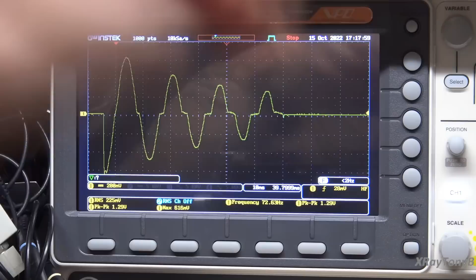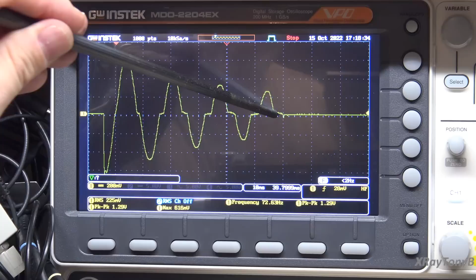So when we get out to about the fourth pulse, you're just a little bit over 20 volts, let's say 22, 23 volts. So 23 volts divided by, let's say, 2 ohms, it's down to about 11 amps, or even less than that. So it's pretty low. And by the time the next one crosses over, the little relay, right about here, is where the relay kicked in, right down about 5 volts or so.